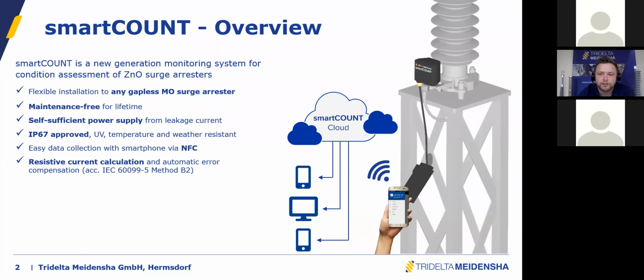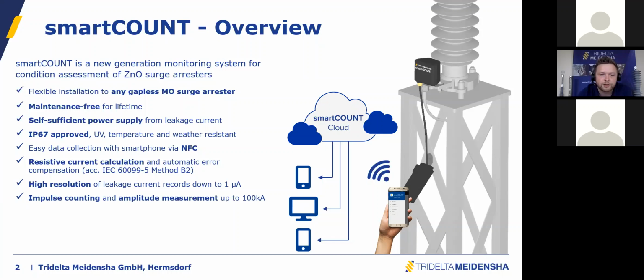NFC is a new technology which we are using to read out the data. And one important point is the resistive current calculation, which is not only state of the art. I would say it's the most modern way to calculate resistive current. I will tell you later, of course, according to the IEC standard. We have a very high resolution of down to 1 microamp, and also impulse counting and amplitude measurement is of course one important feature of the device.